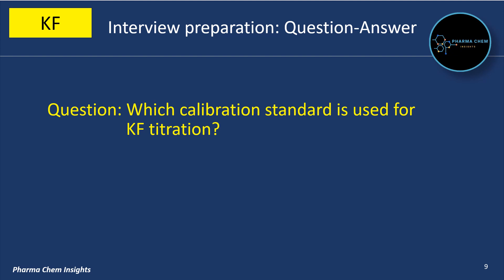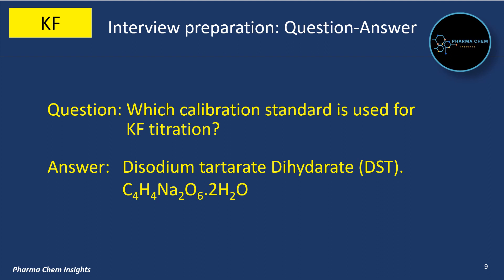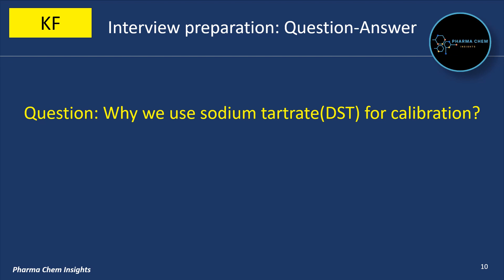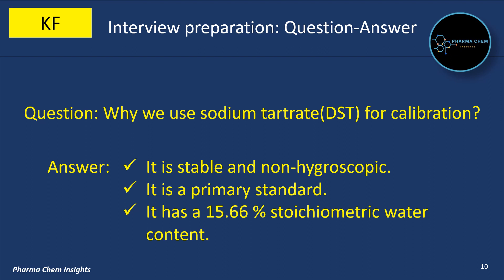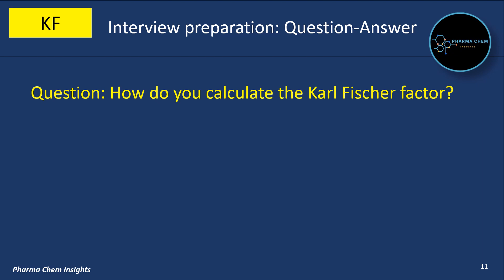Which calibration standard is used for KF titration? Disodium tartrate dihydrate (DST) is used for calibration of KF titration. Its molecular formula is C4H4Na2O6 · 2H2O. Why do we use disodium tartrate DST for calibration? It is stable and non-hygroscopic. It is a primary standard and has a 15.66% stoichiometric water content.